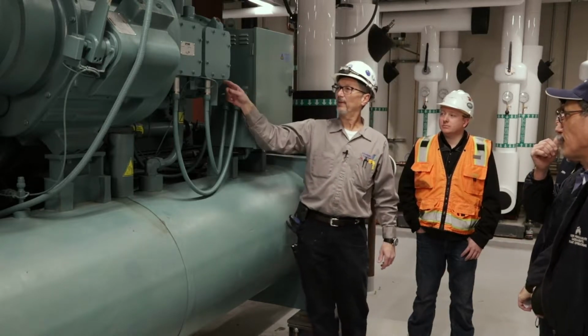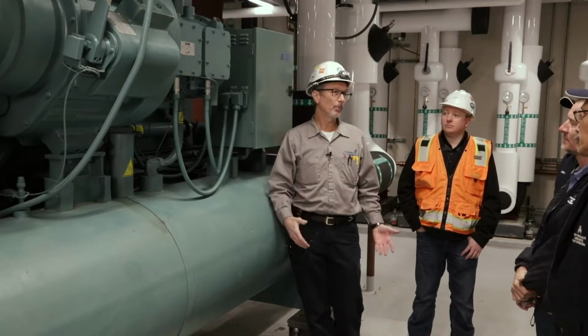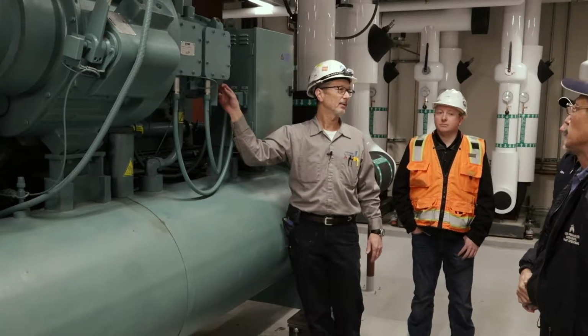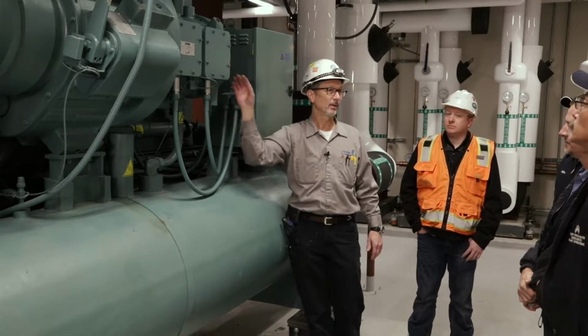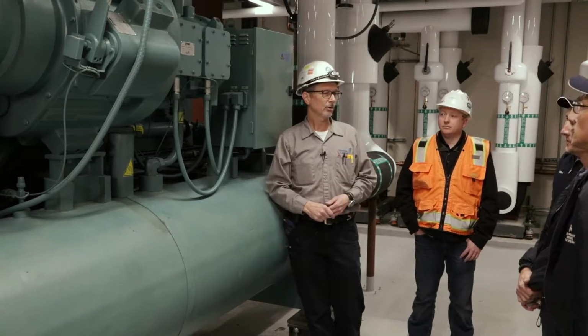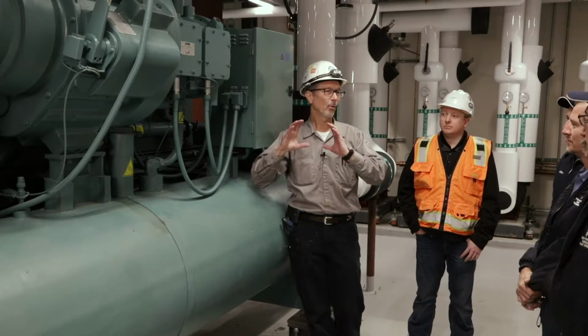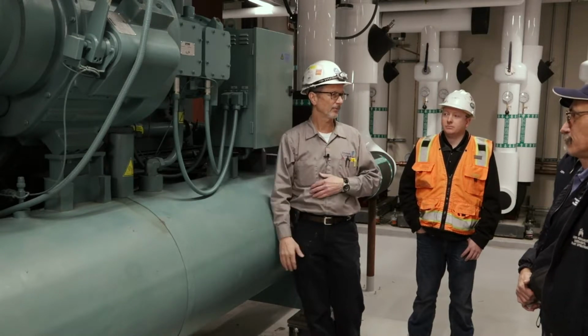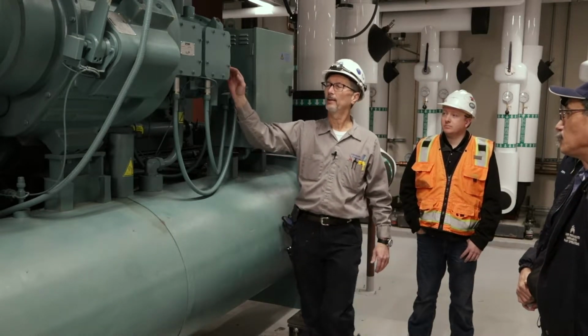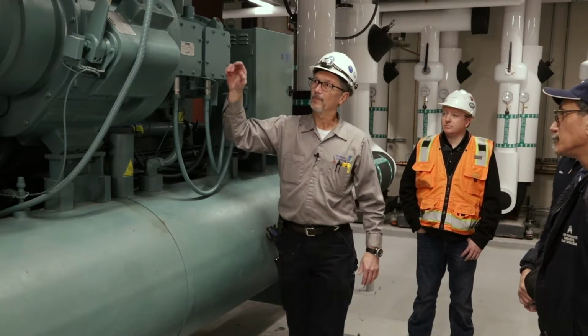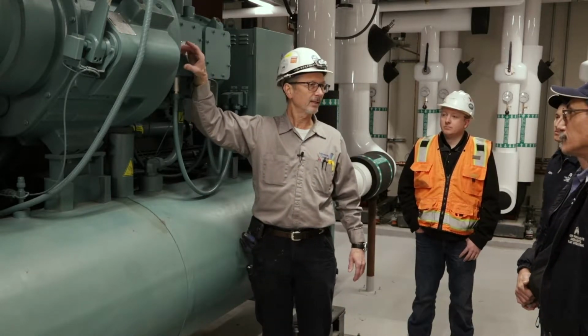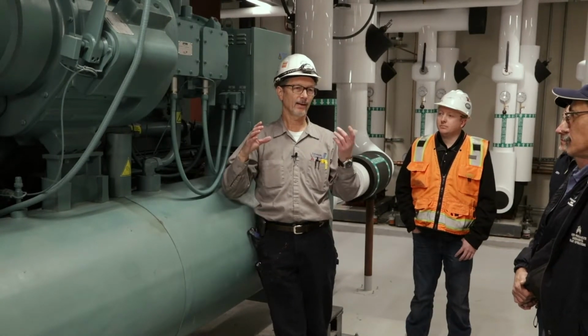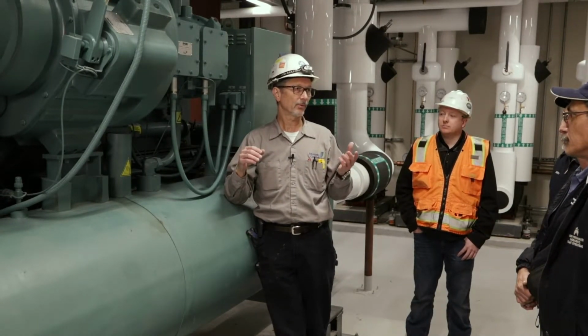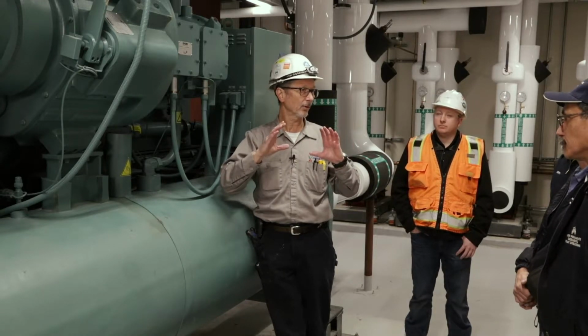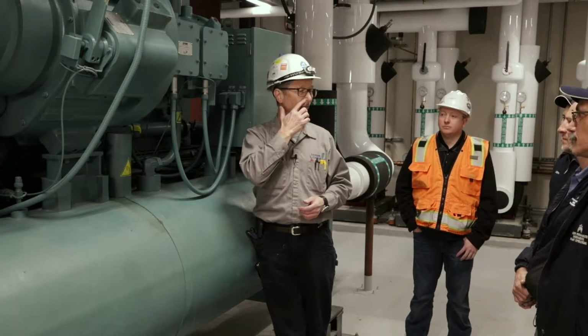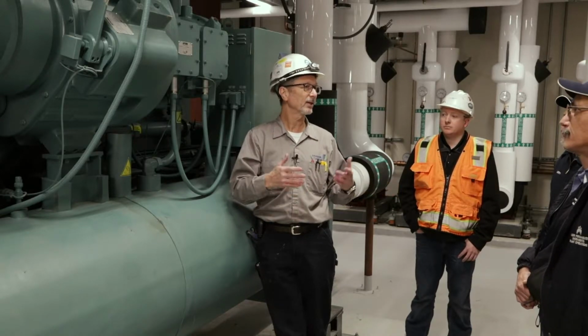And the other thing is, the other chillers that you're used to are an open drive, whereas this is a semi-hermetic. The refrigerant is around this motor. Compared to YK, it's open drive. You have an open motor with a shaft seal separating the refrigerant. So this is semi-hermetic. And then the impeller is a direct connect impeller, where you only have a 3,300 RPM machine, a motor, you can get 8,000 RPM off of YK like that with the gear.